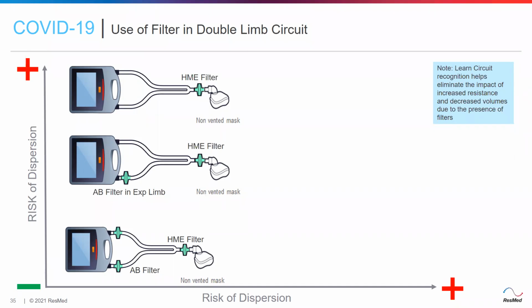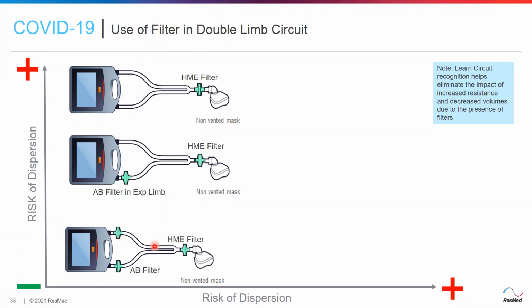Fine. So if we talk about the double limb circuit, this slide shows the risk of dispersion based on the placement of filters at various limbs of a double limb circuit. So the least risk of dispersion would be seen in this kind of circuit where we are using AB filters at the expiratory as well as the inspiratory limb, and an HME filter just after the mask. Fine. So this would ensure that there is least risk of dispersion. Fine. This circuit shows that there is an HME filter placed just after the mask, and in the expiratory limb we have placed an antibacterial filter. So the risk of dispersion is more than in the circuit where we have placed three filters. Fine. In case we are placing only one HME filter after the mask, it has the maximum risk of dispersion, although lower than no filter at all.